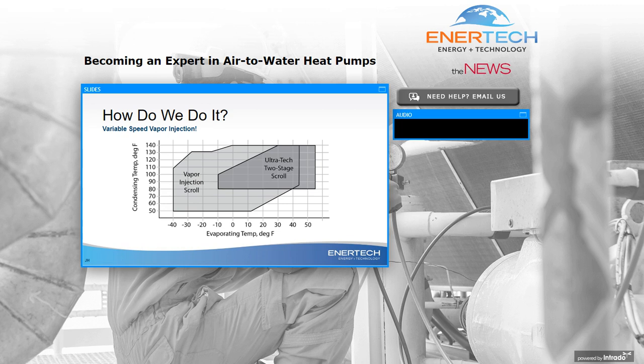How do we do it? We're using a variable speed scroll with vapor injection. The two graphs you see here on the chart show an Ultratech two-stage scroll. That would be a typical heat pump compressor, and it's used very, very widely in the industry. The vapor injection scroll is designed for much colder evaporating temperatures. So we're able to run way down at those cold temperatures and still have very good capacity and very good efficiency. It's really like a turbo boost almost. It's a little counterintuitive. It's cooling the compressor down, but that's what it's designed to do. So when we have very, very cold temperatures outside and very warm water temperatures inside, that vapor injection helps keep the compressor running at a temperature where it's going to be most efficient and have the highest capacity. So it's pretty neat technology with vapor injection.